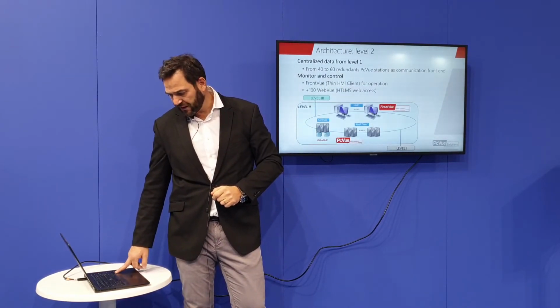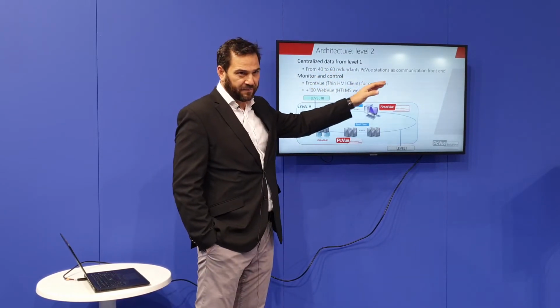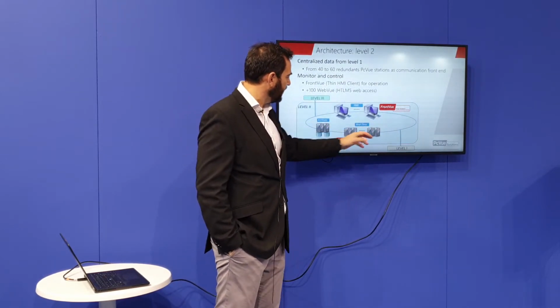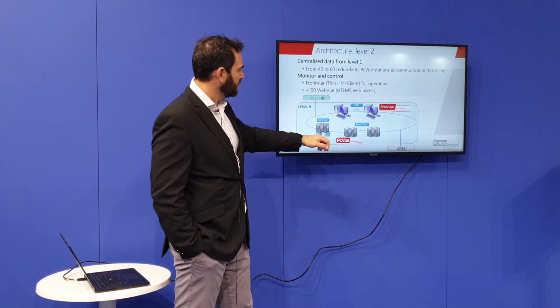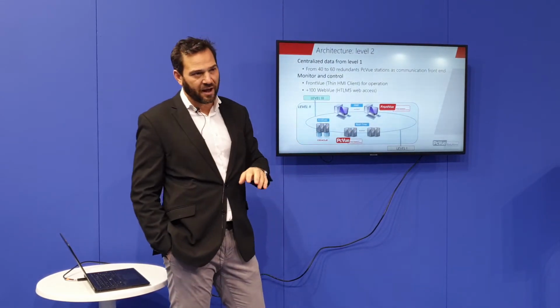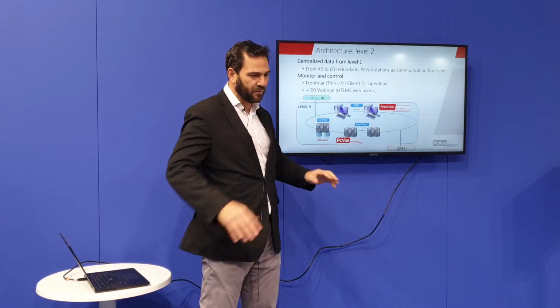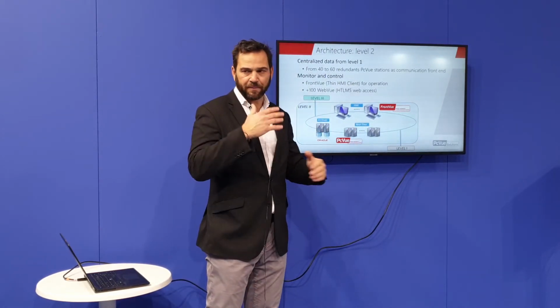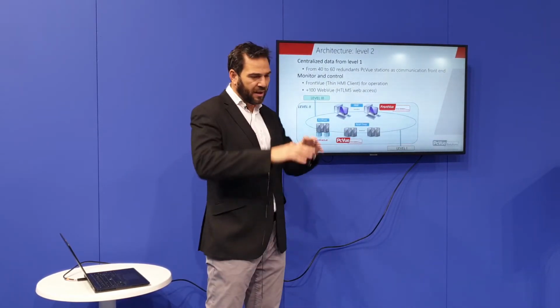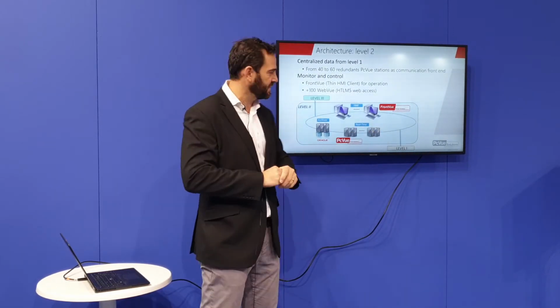In the control center we have from 40 to 60 redundant servers, depending on the control center. These are the VMs that are running, getting data from the field. We have an association of redundant servers, as we really need stability and high availability of the system. Each server gets data from a dedicated area, so we can do maintenance on the system. For example, those 2 servers will look at Spain only, 1 on France, etc., from the control center.